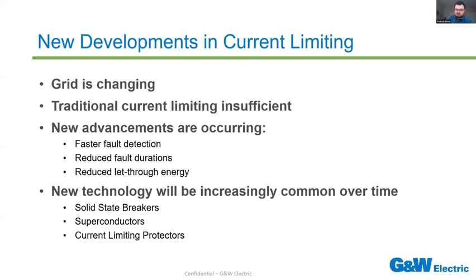So once again, just going over before, a lot of the new developments are occurring in the current limiting landscape, driven by the fact that the grid is changing, and a lot of our traditional current limiting devices are being found to be insufficient in a lot of cases. As a result, you're seeing a lot of new advancements continuing to come out, from both faster fault detection, reduced fault durations, and reduced let-through energy. We're going to highlight some technologies that are going to be increasingly common over time. Maybe not something that you would see every day or even most of the time in wherever you work, but these technologies are going to play a growing factor in the future of the grid. Those are solid state breakers, superconductors, and current limiting protectors.